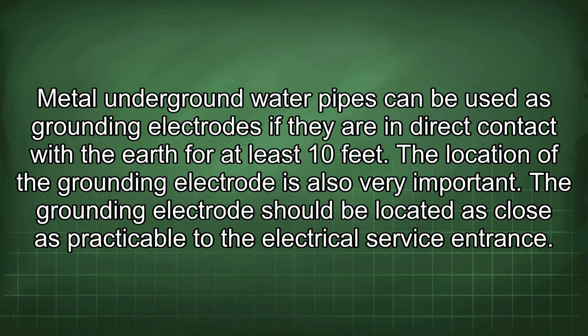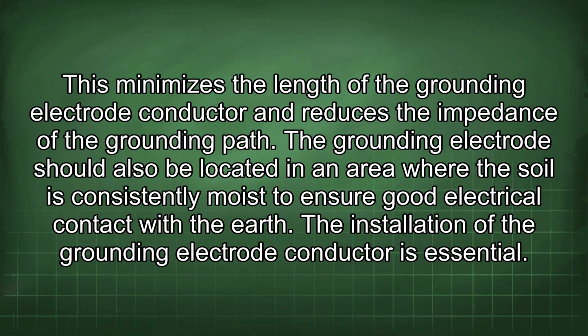The location of the grounding electrode is also very important. The grounding electrode should be located as close as practicable to the electrical service entrance. This minimizes the length of the grounding electrode conductor and reduces the impedance of the grounding path. The grounding electrode should also be located in an area where the soil is consistently moist to ensure good electrical contact with the earth. The installation of the grounding electrode conductor is essential.